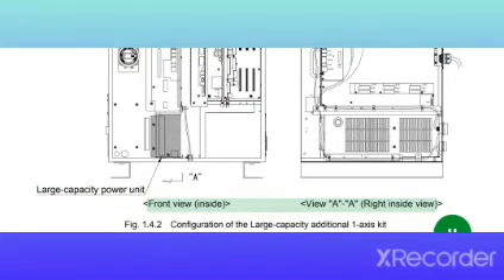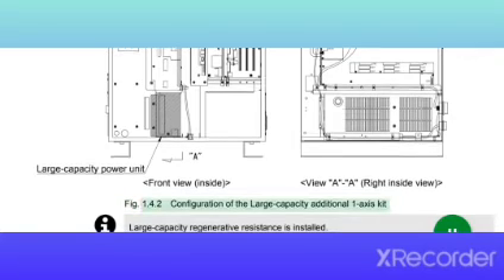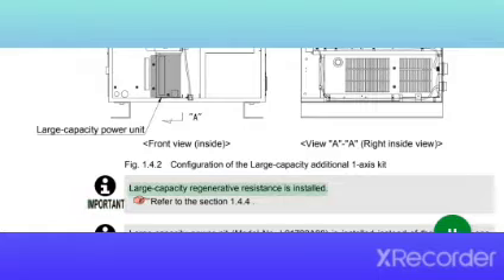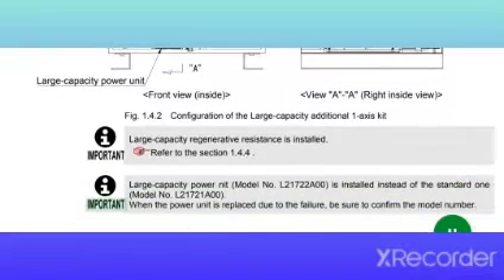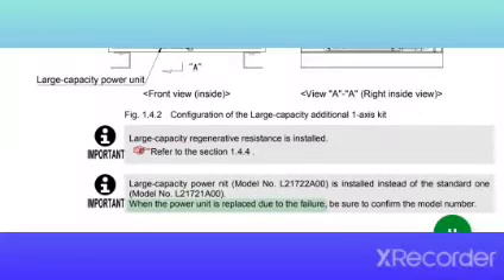Large capacity additional 1-axis kit, large capacity power unit. Fig. 1.4.2 Configuration of the large capacity additional 1-axis kit, front view, inside view A, right inside view A. Important: large capacity regenerative resistance is installed. Refer to section 1.4.4. Important: large capacity power unit model No. L21722A00 is installed instead of the standard one, model No. L21721A00. When the power unit is replaced due to failure, be sure to confirm the model number.